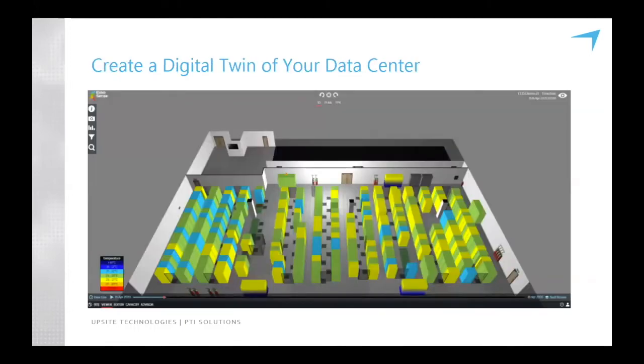So here's some images from the software. This is an image looking at the room, and the colors, of course, represent the intake temperatures on the cabinets. One of the things I want to mention about this is you'll see that every cabinet in this room has a color, which means every cabinet in this room has a sensor. This solution as a comprehensive solution was developed with very low cost, very competitively priced temperature sensors, but that's not the point of it. The point of it is to gather that information through the granular deployment of sensors so that these powerful analytics can be played out.